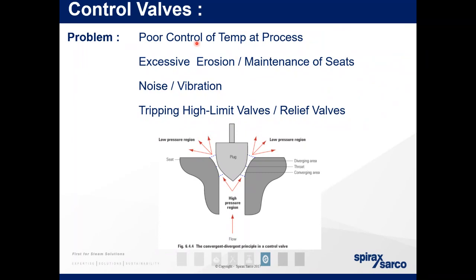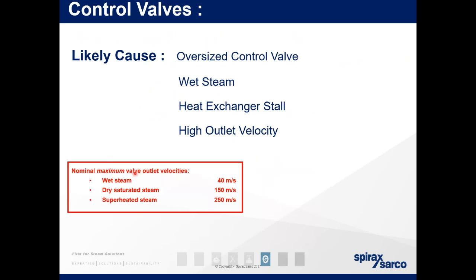We'll see excessive erosion and maintenance of seats. So the faster the velocity through the valve, the more erosion you'll have on the valve seat. So we recommend, if I just go to the next one, we recommend these nominal velocities for things like in any control system. So wet steam would be 40 meters per second, dry saturated steam up to 150 meters per second. However, these last two figures I would suggest is for a control valve only, so it's not for your system. And superheated steam 250 meters per second. So likely causes of these overall too high velocities can be oversized control valve, wet steam, heat exchanger stall, and high outlet velocity. Do we have any questions at this point?